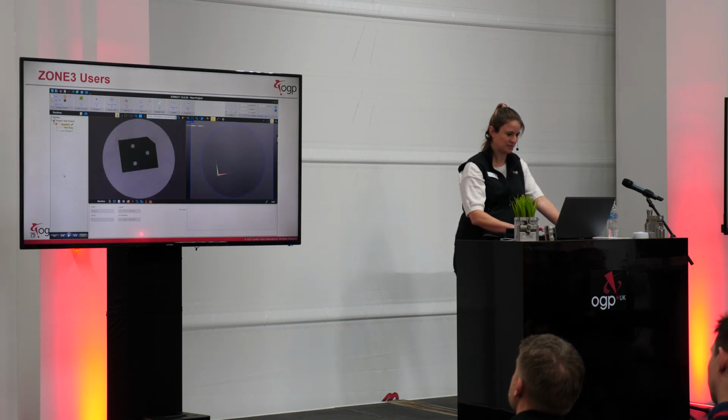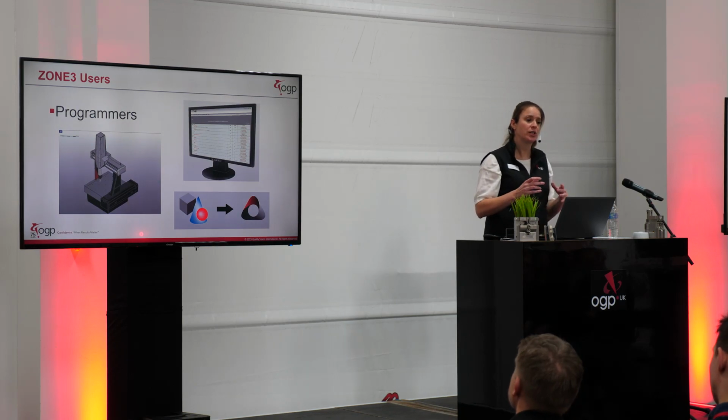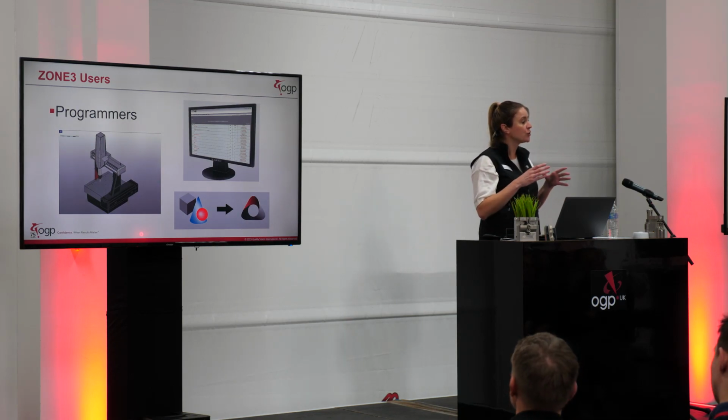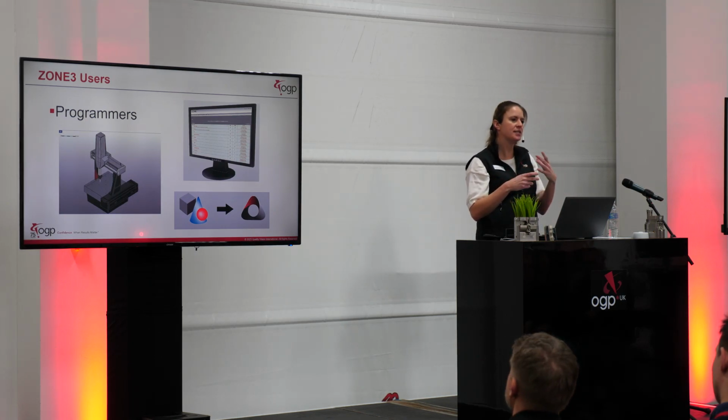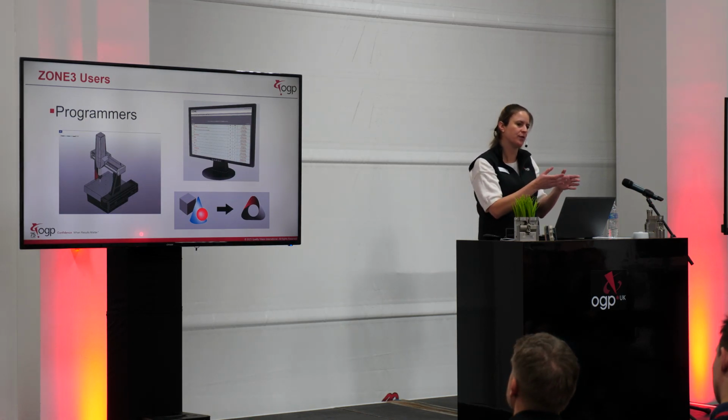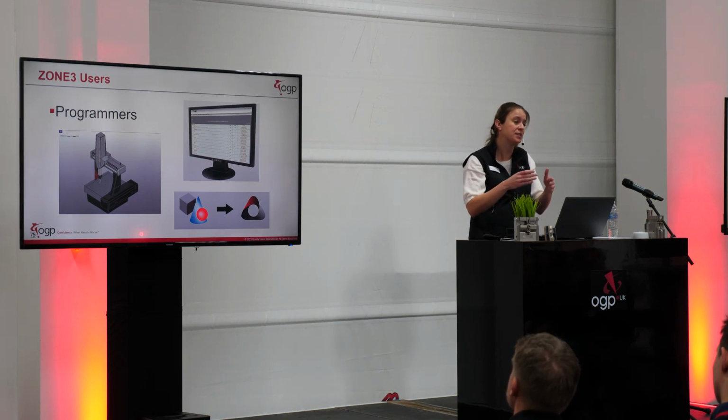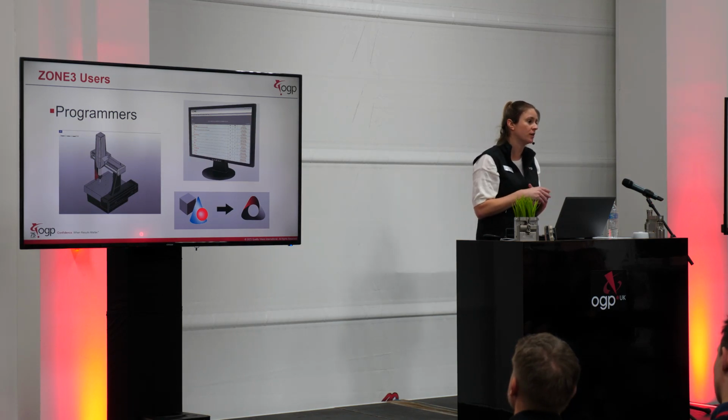The Feature Extractor, so we originally made that tool for our large field of view systems that had that 100mm field of view. But since then, we've enhanced it to handle multiple fields of view like you saw in the video and actually scan the stage. So people using SmartScopes have started using it as well, and it's been very helpful for programming.